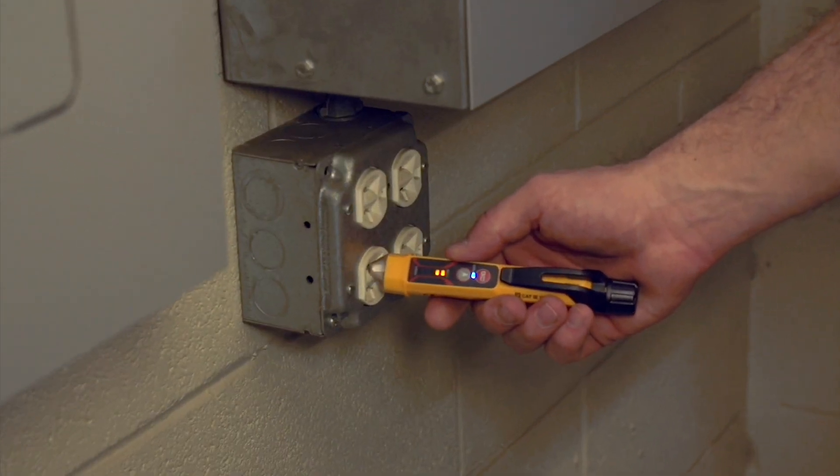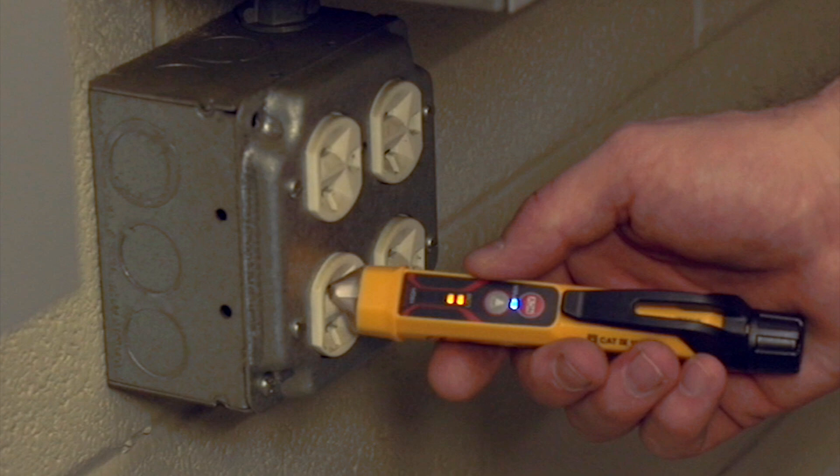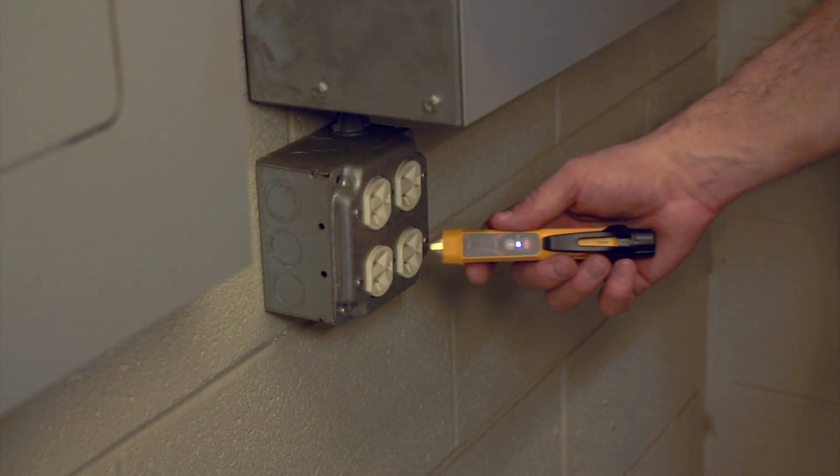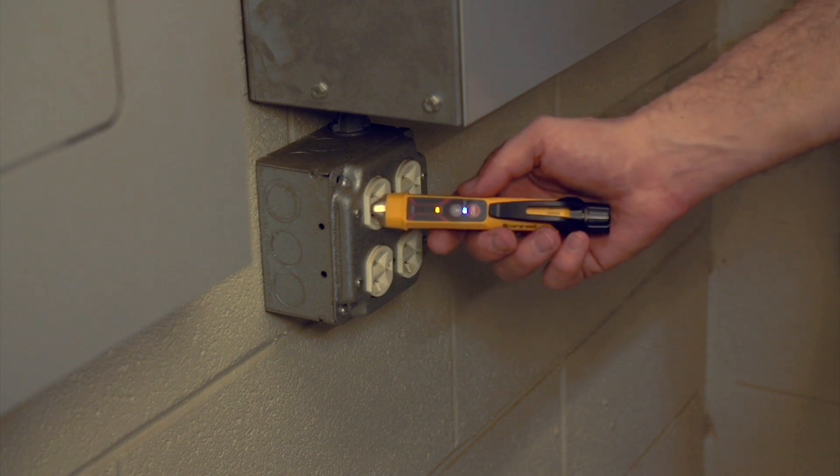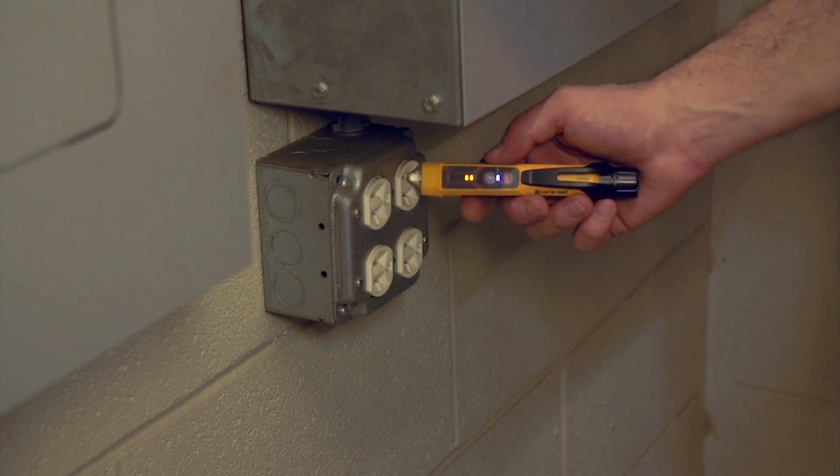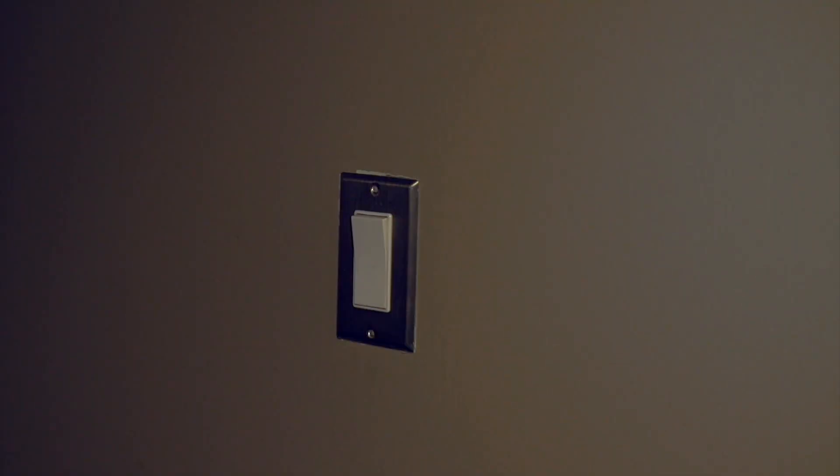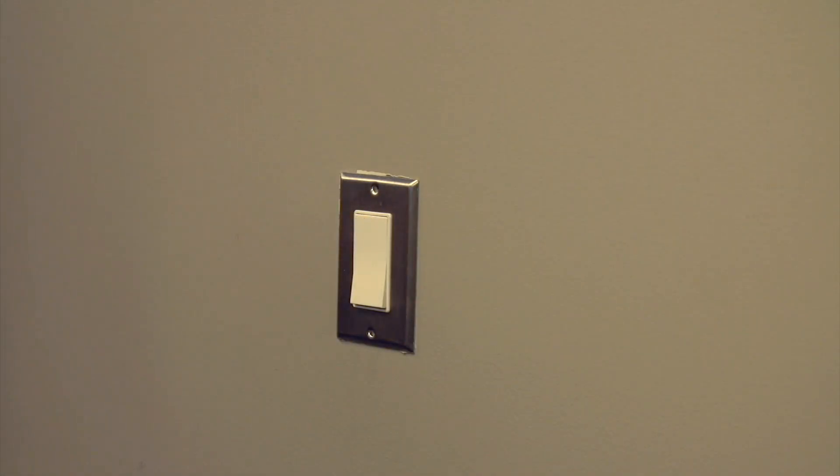When testing an electrical outlet or receptacle, the tip just needs to be placed on the faceplate near the smaller plug slot. But it's a good idea to test all slots on the outlet or receptacle just in case they were wired incorrectly, differently, or on different circuits. If the receptacle is connected to a wall switch, make sure the switch is on during testing.